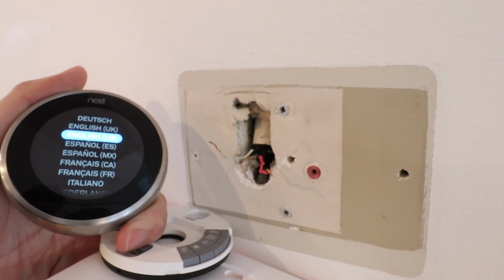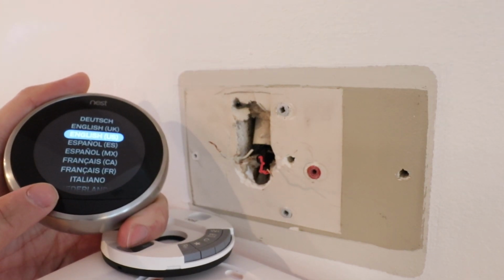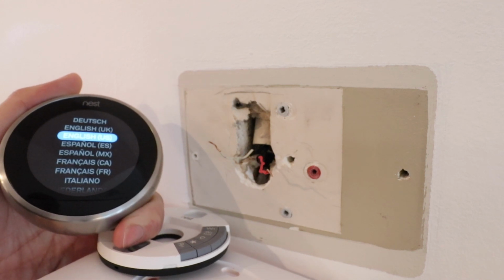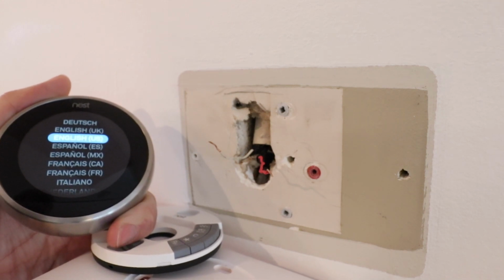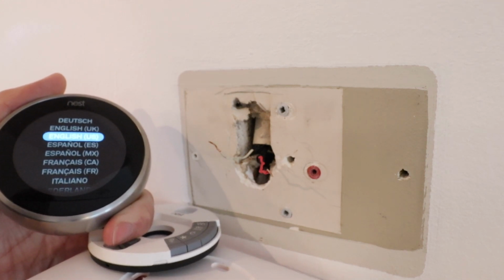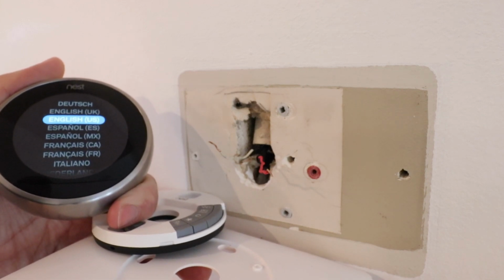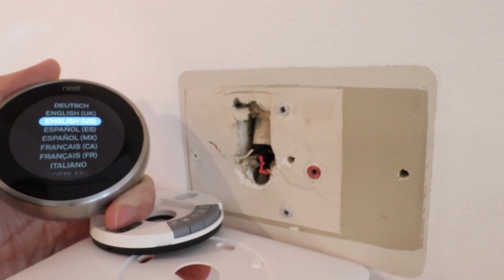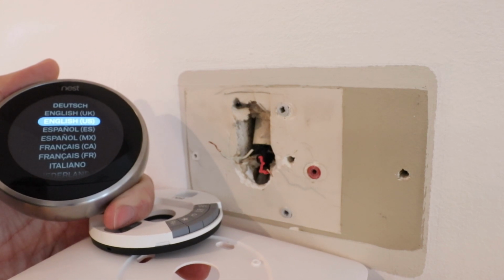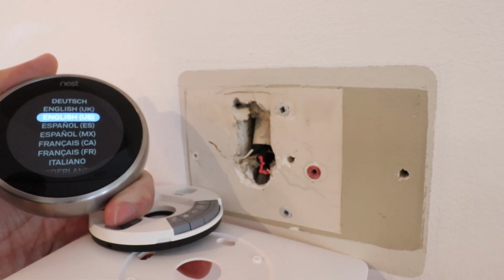Something important to note is that the Nest Gen 3 typically does not require a common wire for boiler heating systems or heat-only systems. Probably about 80 to 90% of two-wire thermostat systems that have a heat-only or boiler-only system do not require a common wire, in my experience.